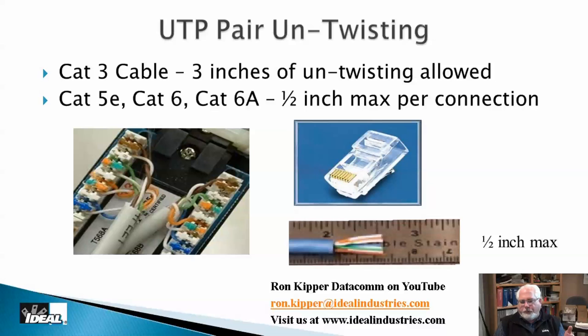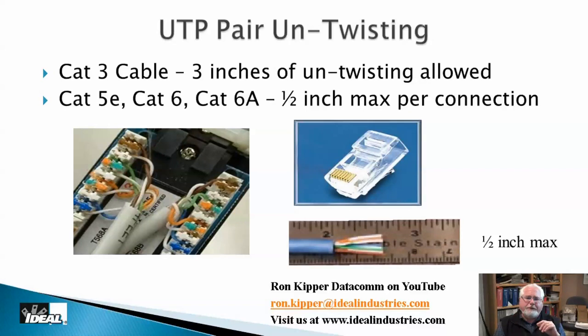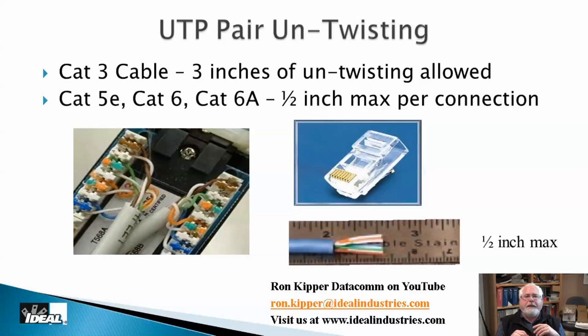When terminating cables — putting a connector on the end at a patch panel, jack, or modular plug — the standard says to leave no more than a half inch of untwisted conductor at the connection. You can bend the cable in many cases, but don't untwist it. You can never re-twist it the way the machine did, and technically it should be twisted at a very specific rate throughout the entire cable length. Half inch is the maximum untwisted length allowed per connection.